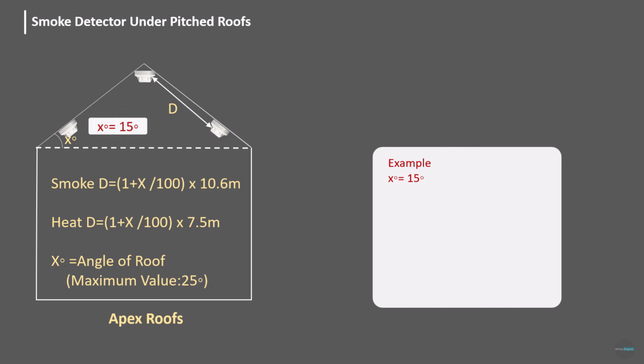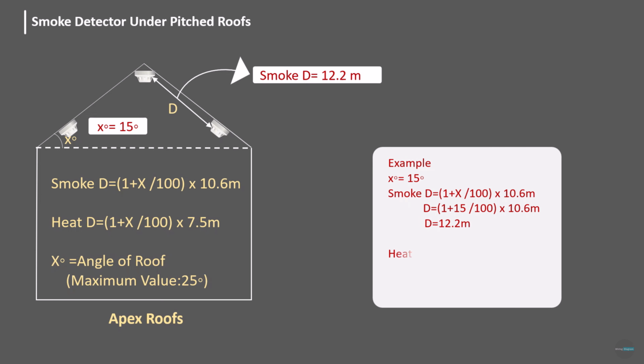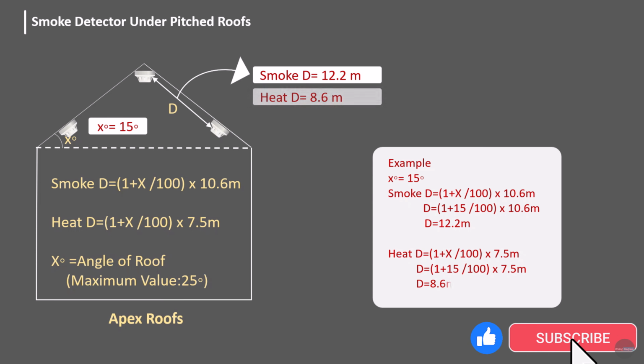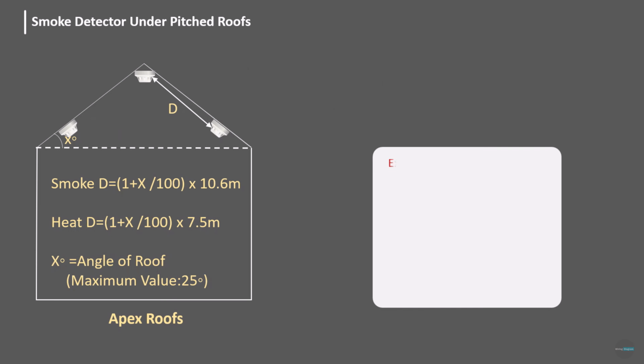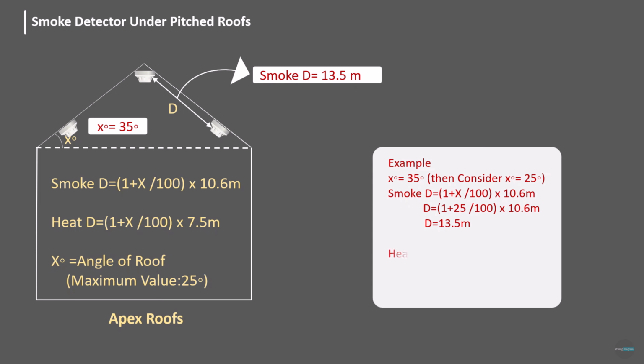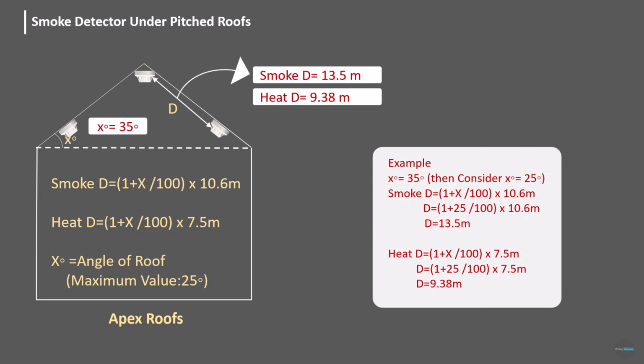Here, if x is 15 degrees, then smoke detector distance equals (1 + 15/100) × 10.6 meters, which equals 12.2 meters, and heat detector distance equals (1 + 15/100) × 7.5 meters, which equals 8.6 meters. If x is 35 degrees but we consider the maximum of 25 degrees, then smoke detector distance equals (1 + 25/100) × 10.6 meters, which equals 13.25 meters, and heat detector distance equals (1 + 25/100) × 7.5 meters, which equals 9.38 meters. So friends, we learn how to design detectors in an apex ceiling.